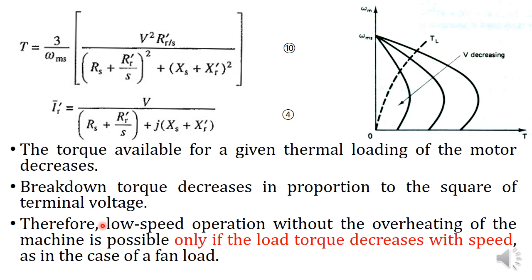Low speed operation without overheating of the machine is possible only if the load torque decreases with speed, as in the case of a fan load.